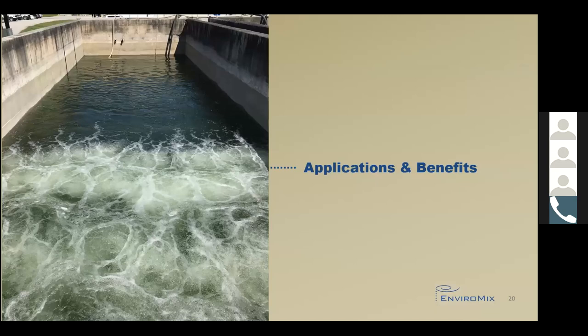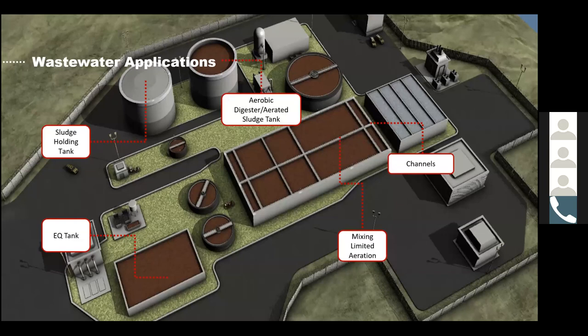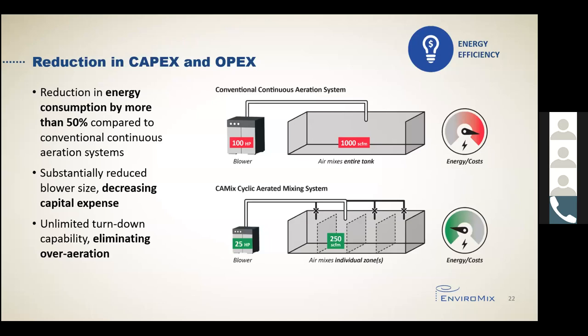A CAMix system can be used in any mixing limited application in a wastewater plant, or where mixing is required but the process only needs a small amount of oxygen. The most popular applications are sludge storage, equalization tanks, and channels. The most obvious benefit of CAMix is the reduction in both capital expenditure and operating expenditure. By cycling the air from one zone in a tank to the next instead of applying it to the entire tank 24-7, there is a reduction in energy consumption by more than 50% in most applications. Additionally, the size of the blower will be dramatically reduced, resulting in capital savings, and there is unlimited turndown capability which results in elimination of over-aeration and wasted energy.